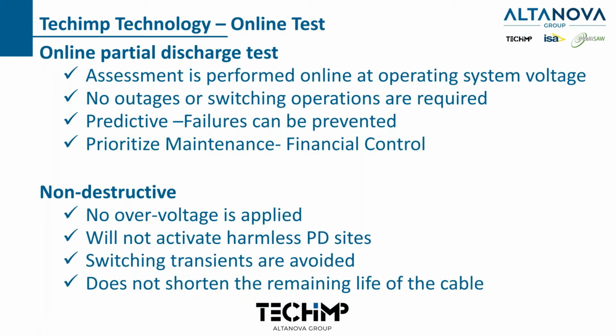So let's talk about the testing. Again, just to review, it's done online at system voltage. We don't apply any voltages or any signals onto the cable. There's no switching required, no interruptions. What's good about this testing is it helps our customers predict failures and prevent unplanned outages. Of course, that helps them prioritize the maintenance and control their finances. So it basically tells you what needs to be addressed and what doesn't.